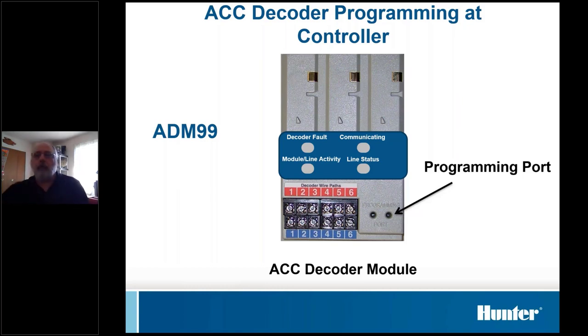So, we're pretty much the only people that are doing this. What we do with our decoders is we assign a station number to the decoder, and then the controller just sends out a command to turn on that station number. Whereas in the rest of the systems, and in our older systems too, each decoder had its own unique serial number. And these ones actually have a serial number, we just don't use it.